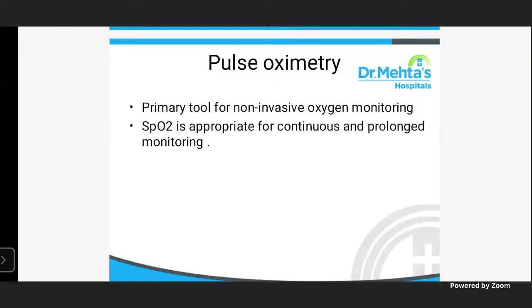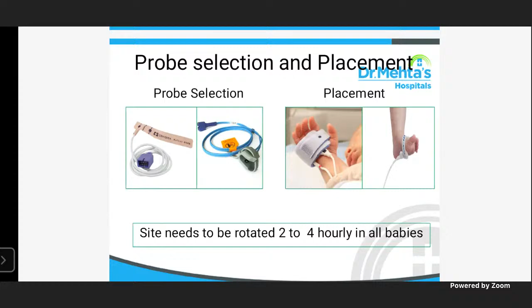So, probe selection and placement. We can select a disposable or reusable probe. And placement is, as I already informed, on the hand of the baby or the foot. It has to be rotated every second hourly or fourth hourly in all babies, because if it is there for a long time, it will compress the site of the probe. So there won't be any blood circulation, and you won't get the correct saturation. Whenever you handle the baby, at maximum every second hourly to fourth hourly, you have to change the probe site and check, because it can create a burning sensation or skin peeling. So we have to change the probe site every second hour.